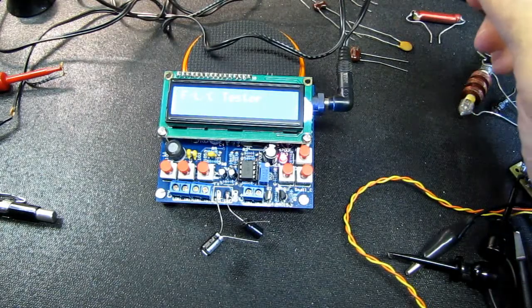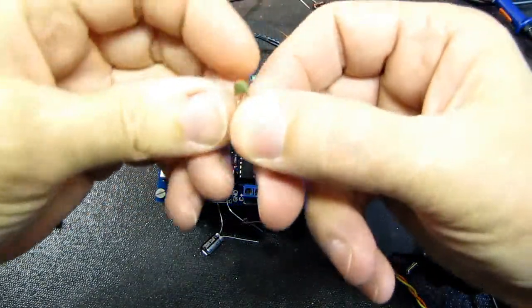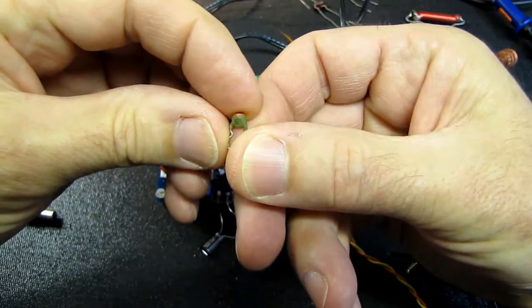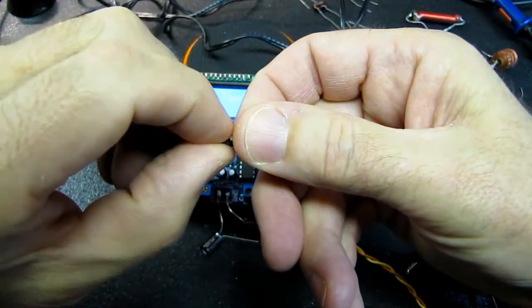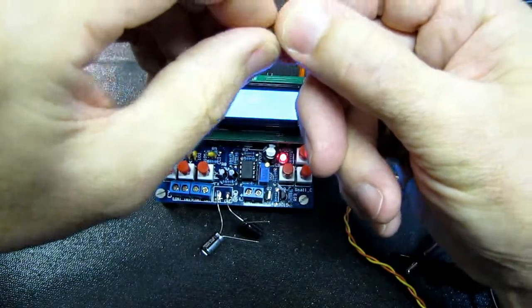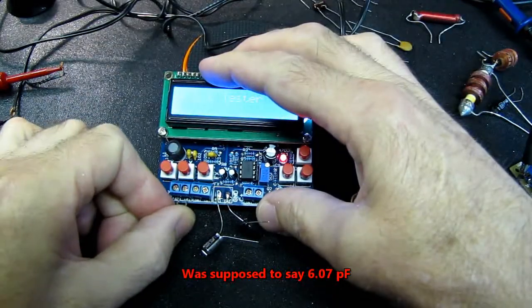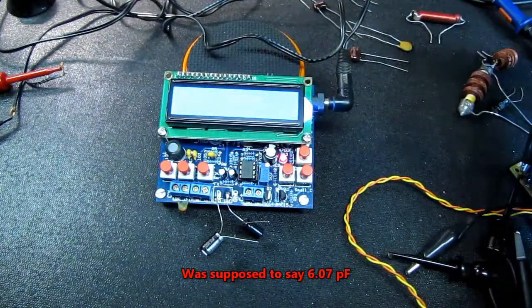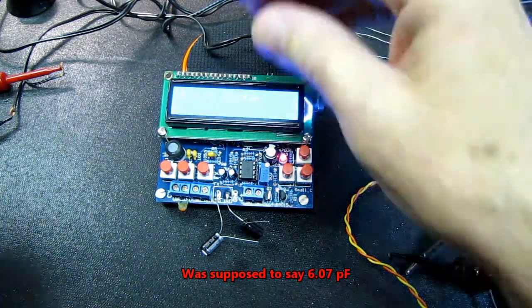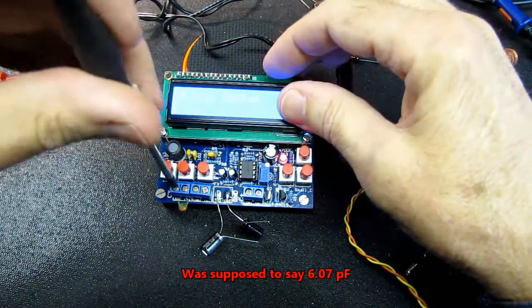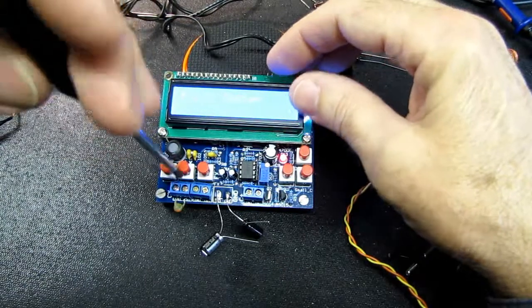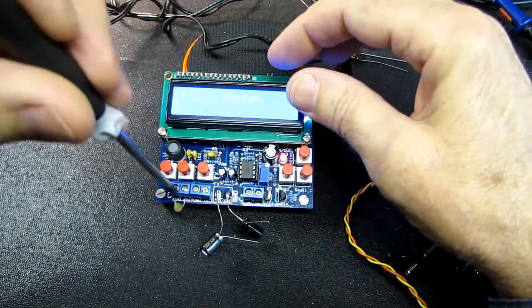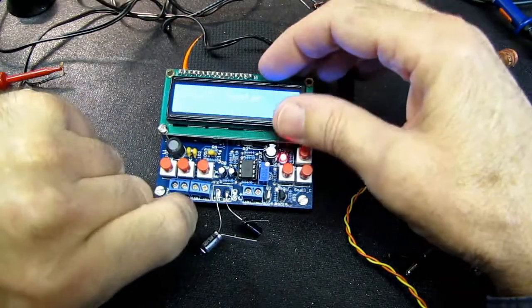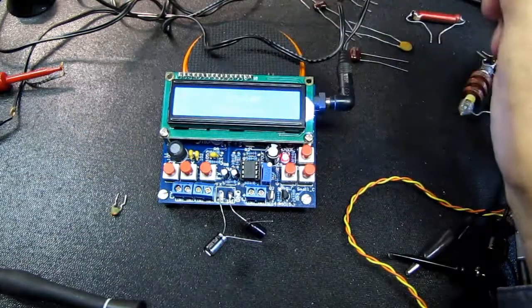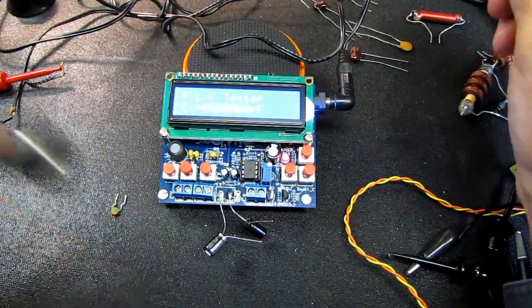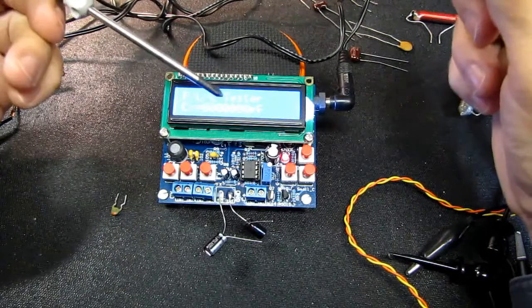Now, I have a bunch of capacitors here. I have one that's marked 6 picofarad, and I know for a fact it's 6.07 picofarad. I've measured that on my Boonton laboratory bridge, which is extremely accurate. So I'm going to put in the 6 picofarad capacitor. Actually, before I even do that, I'm going to take the capacitor back out of here. I'm going to turn on the capacitance test function, and hopefully you'll be able to see the display well enough.